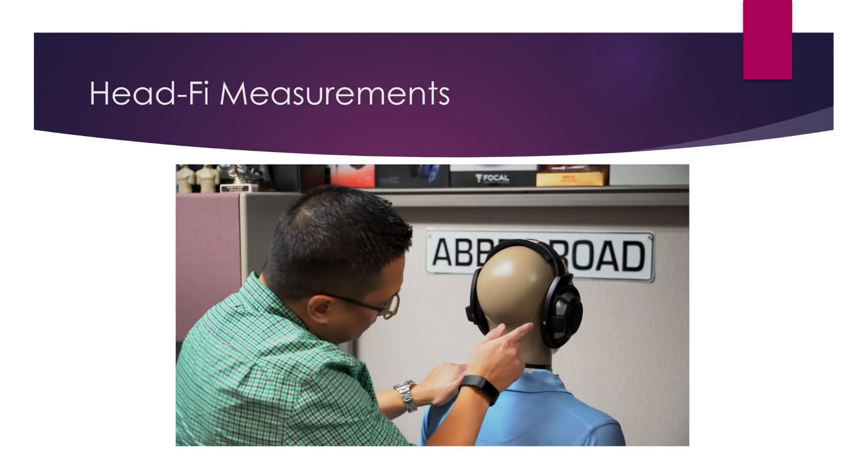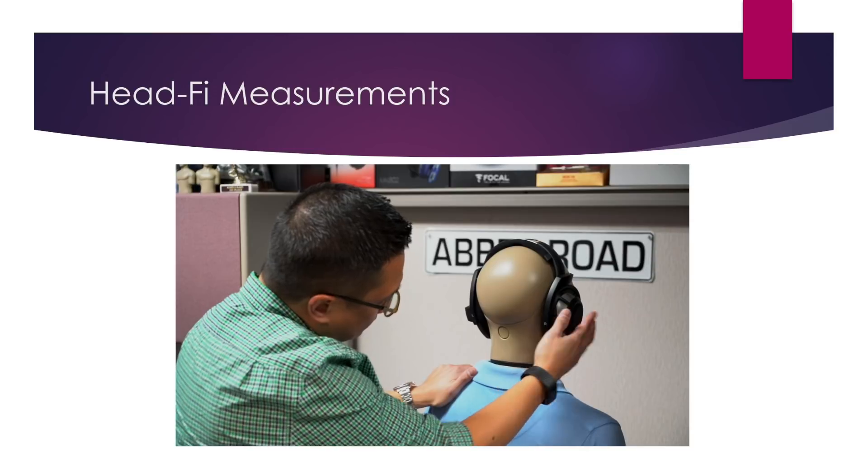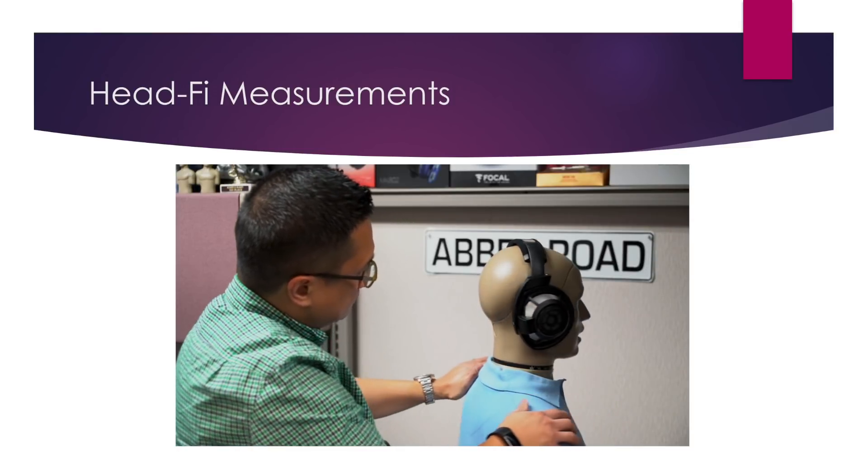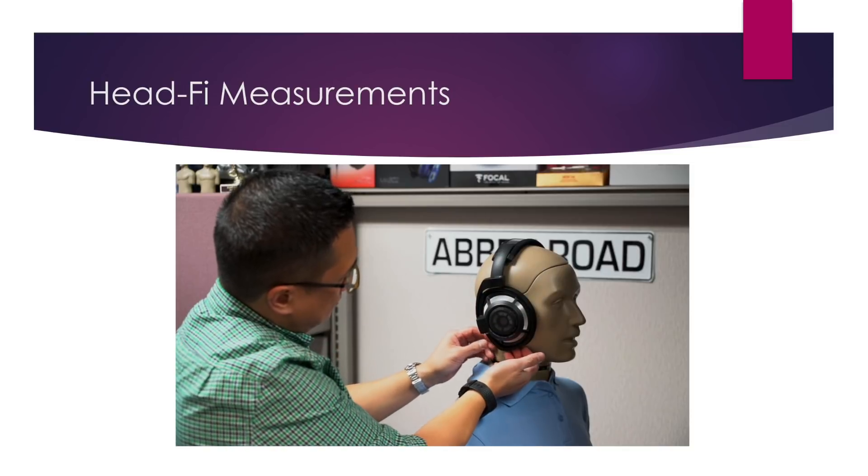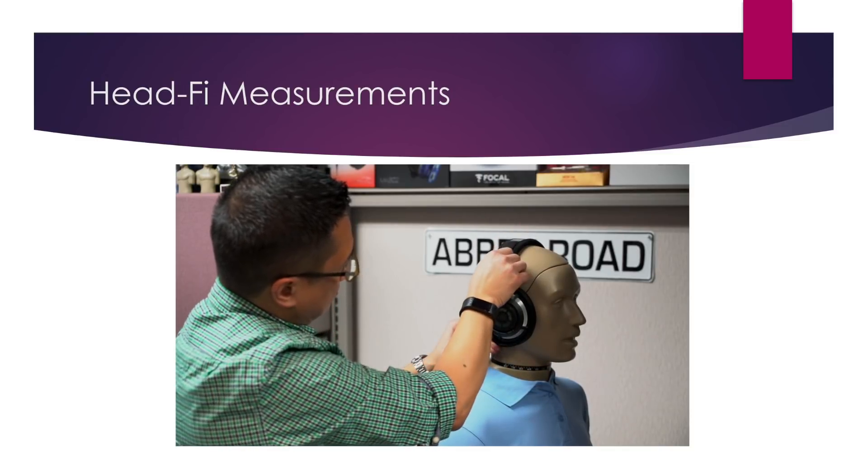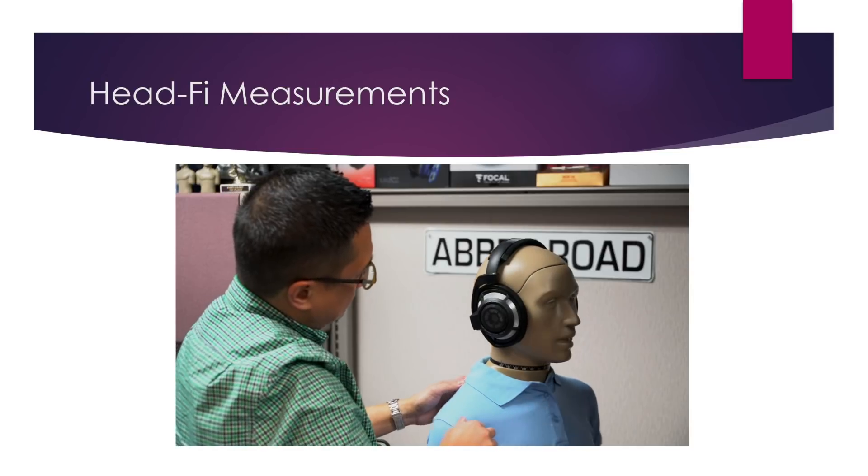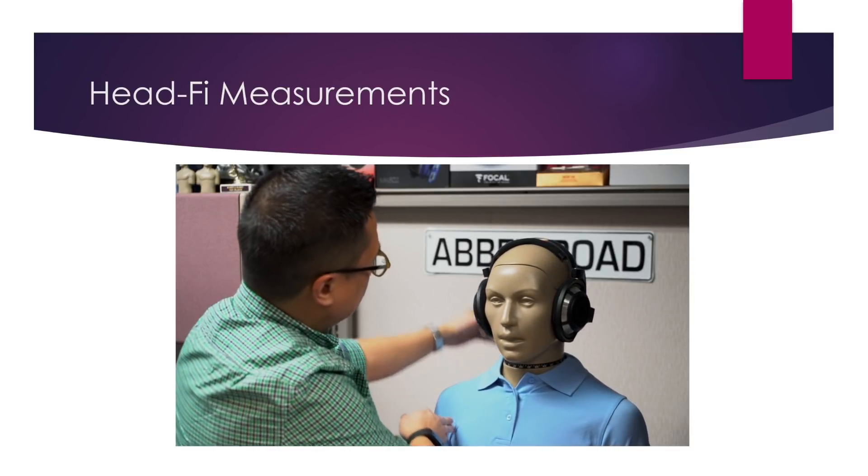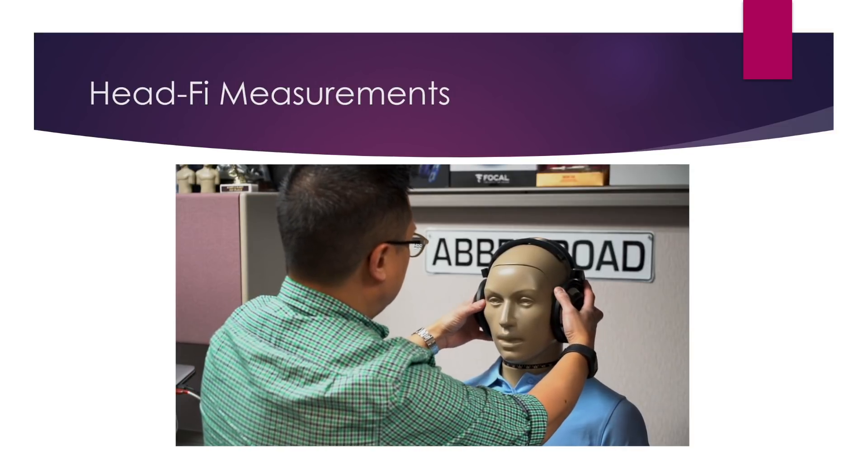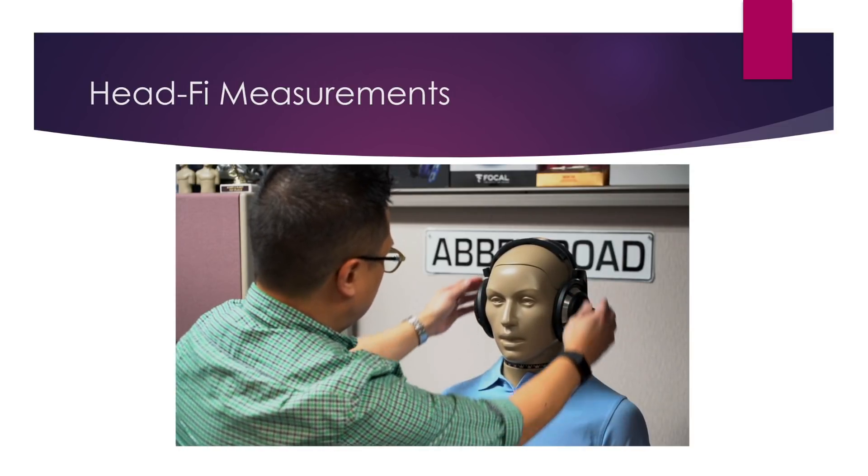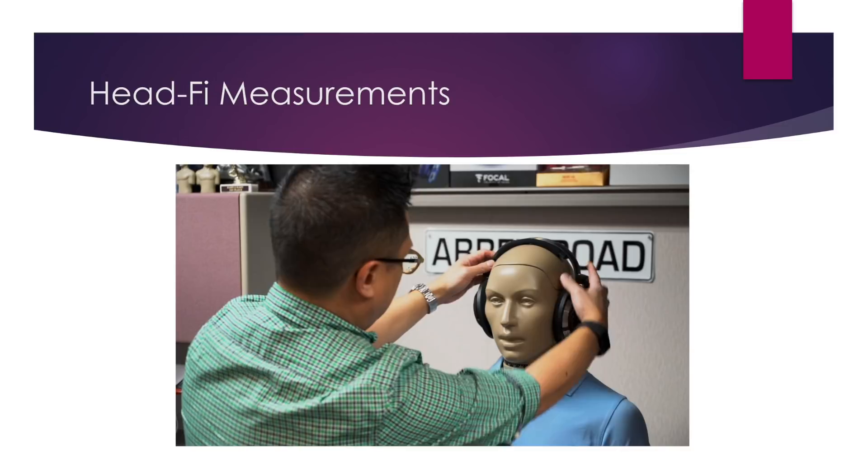Realistic placement of the headphone over the ears and the ear simulators inside the head is critical. As you go higher up in frequency, as wavelength shortens, positional changes, even small ones, can have dramatic effect on the high frequency response. In this video, I'm trying to show the limited range of movement for this headphone that still maintains a seal. So again, I actually like using a more human-like mannequin for measurements for these reasons and for the results that we've gotten. That said, it can take a bit more time to finesse placement on this more human-like fixture.